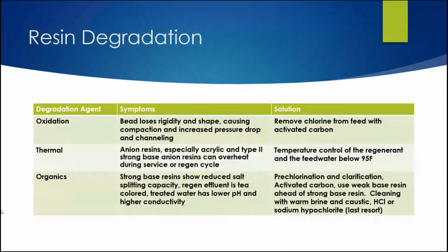The resins can also suffer from degradation. Resins degraded by oxidants, heat, or organic materials will often need to be replaced. If recognized early, changes can be made to prevent further degradation. The real goal is to prevent it from occurring by eliminating the source of the problem.